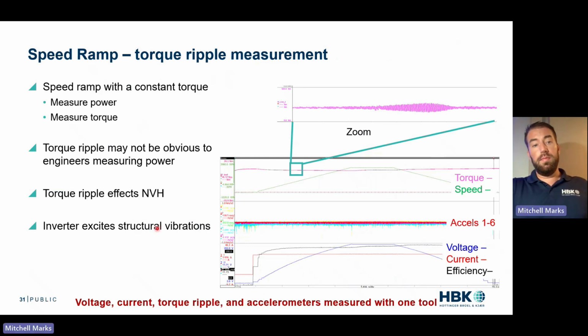Now an example. This was, again, a fixed torque. This is actually the same example I showed earlier. I only have so many, so I do a lot of things with each one of them. We have our torque in pink, we have our speed in green, we ramp speed, we're bringing in accelerometers, and we're looking at our voltages and currents. If we zoom in on that torque, we can see kind of normal torque ripple, and then boom, we hit a resonant point. We hit a resonant point, and there's more than one.